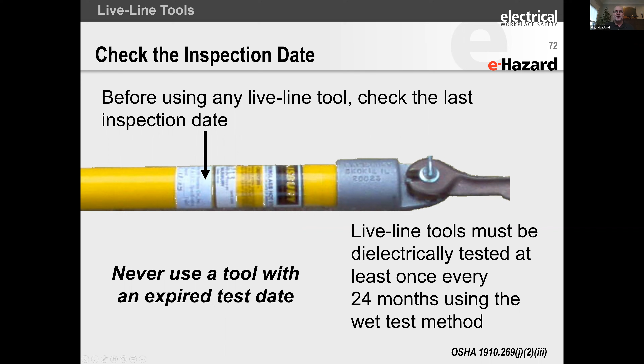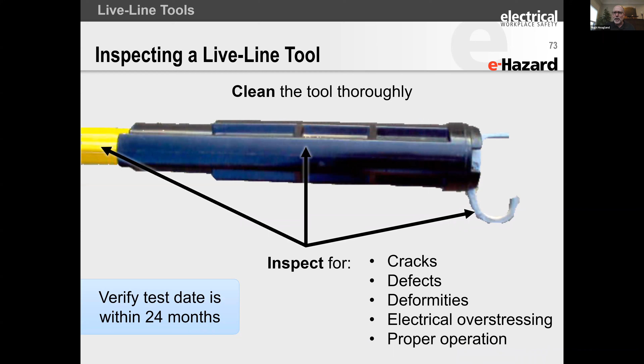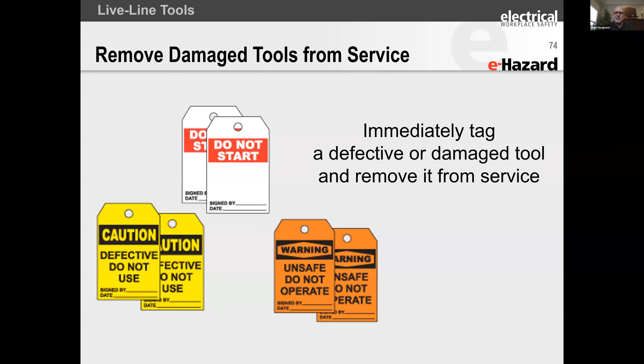They're cleaned and inspected. And so it's really important to take care of these and to clean them only with agents that are allowed for that particular device. See how I'm doing on time. I'm in good shape. Clean the tool thoroughly, verify the test date, and make sure everything is working correctly before you use them. You're inspecting for cracks, you're looking for defects, you're looking for deformities, electrical stressing, and proper operation. Tag damaged tools, take them out of service so they can be repaired, replaced, or destroyed. In some cases, they just have to be destroyed.